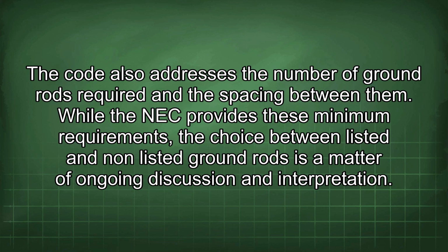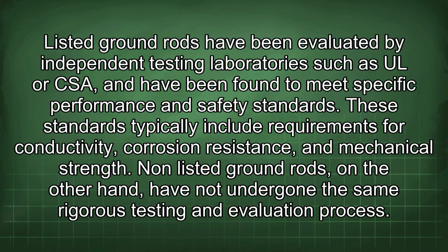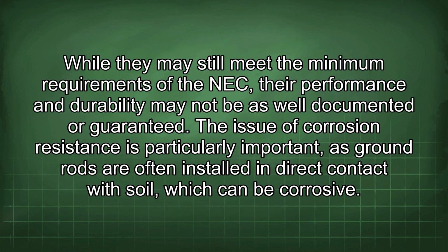While the NEC provides these minimum requirements, the choice between listed and non-listed ground rods is a matter of ongoing discussion and interpretation. Listed ground rods have been evaluated by independent testing laboratories such as UL or CSA and have been found to meet specific performance and safety standards. These standards typically include requirements for conductivity, corrosion resistance, and mechanical strength. Non-listed ground rods, on the other hand, have not undergone the same rigorous testing and evaluation process.